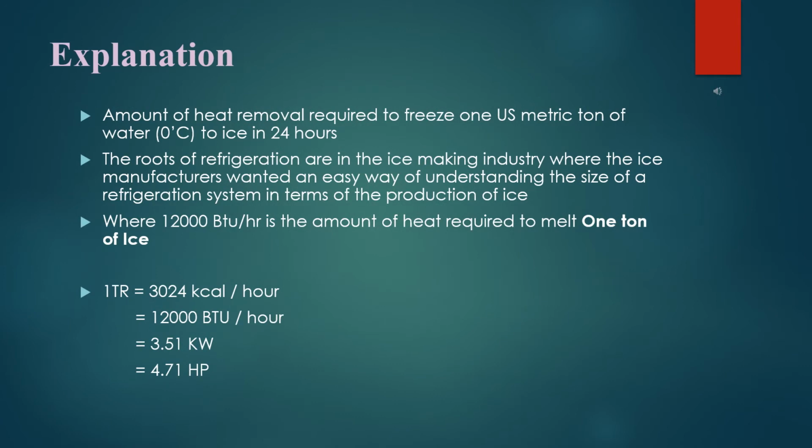It is the heat removal required to freeze 1 US metric ton of water, which is at 0 degrees Celsius, to ice in 24 hours. The roots of refrigeration are in the ice manufacturing industry, where the ice manufacturers wanted an easy way of understanding the size or capacity of a refrigeration system, in terms of the production of ice. In simple terms, if we provide 12,000 BTU per hour of heat to 1 ton of ice, it will melt to water, which is at 0 degrees Celsius, in 24 hours.